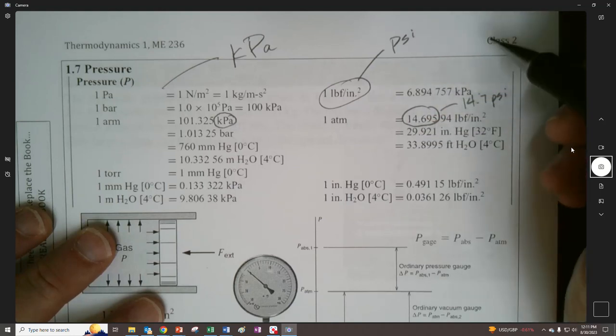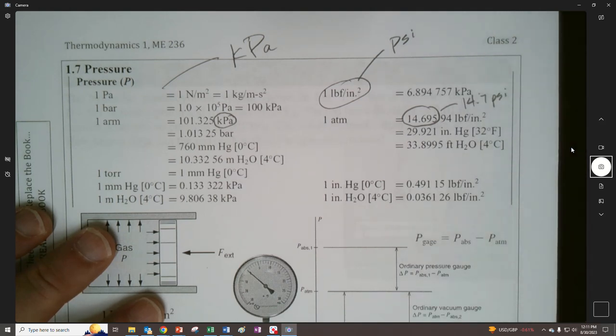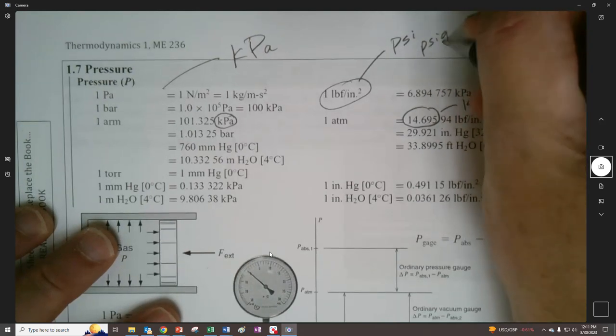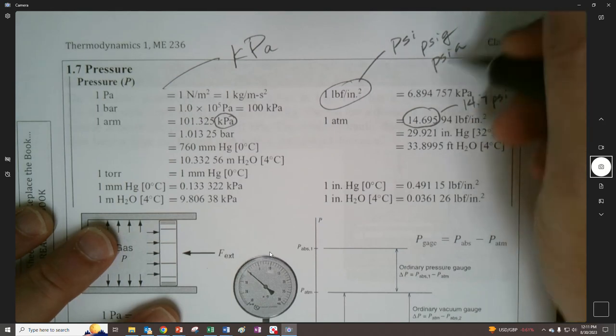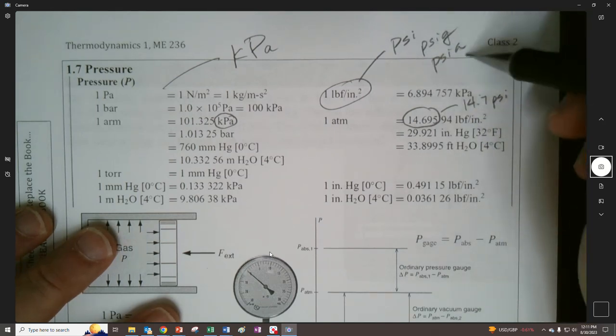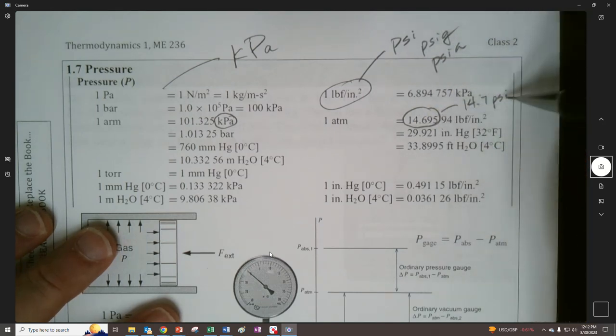I think that's fair to say because the gauge is usually calibrated so that it's at zero when there's no pressure inside the vessel. So what we're saying is it's at atmospheric pressure when it's zero. So you'll see sometimes you'll see psi g for gauge and psi a for absolute, and the difference between these is generally going to be right around 14.7.